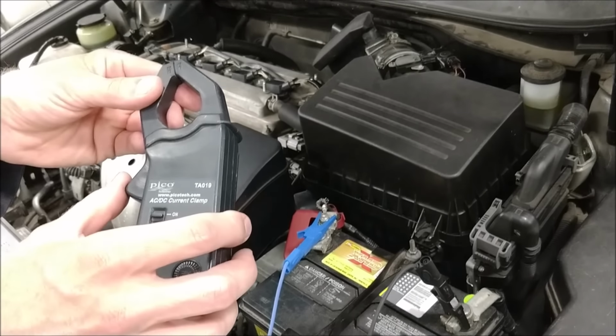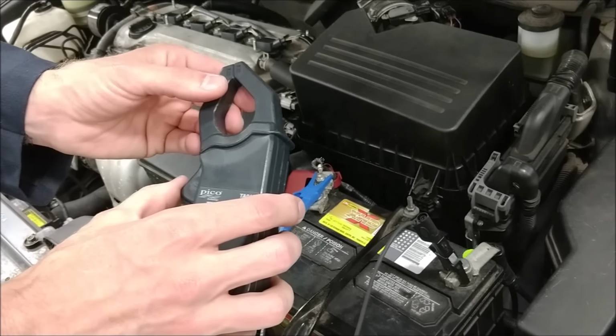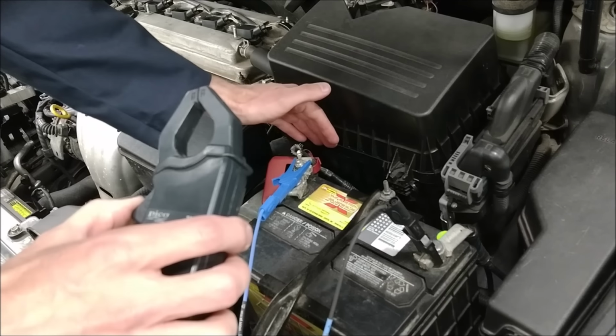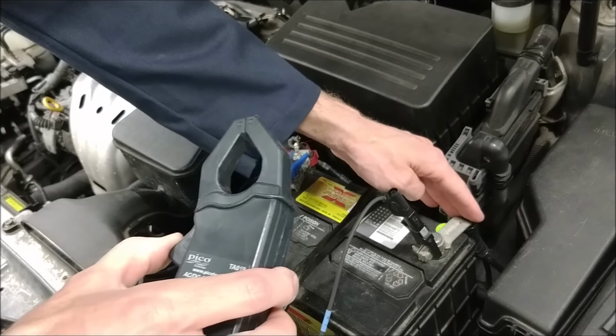Now here's a really important part. I need to make sure I get around all of the cables. It doesn't matter whether I put it on the positive or negative, but if there's more than one cable, I need to get around all of them, observing the polarity of the current probe. This arrow always points the direction of conventional current flow, flowing away from positive or toward negative. So if I'm putting it on the positive cable, I want to get around both cables with the arrow pointing away from the battery, like this.